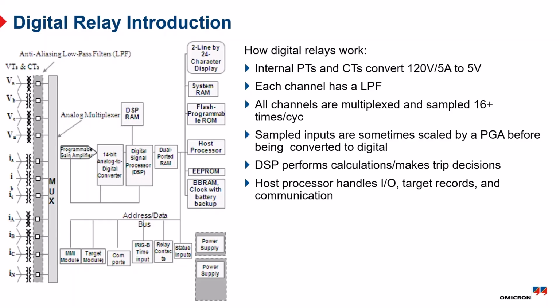Also, any of the digital communications, so 61850, UCA, DNP, even Modbus. Back in these days, it was Modbus mostly in plants, but it handled those communications. Then you have all the supporting pieces: address bus, data bus, memory chips, a flash ROM where the relay's program is stored, HMI, display, power supply, all the rest of that stuff kind of supporting.